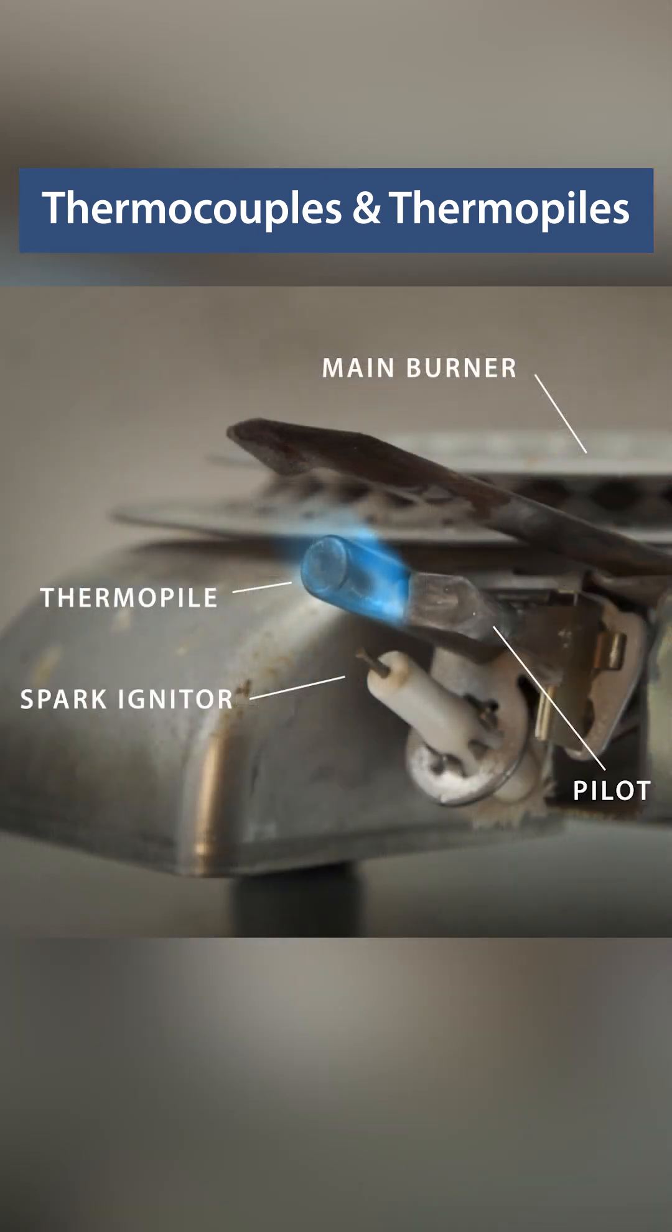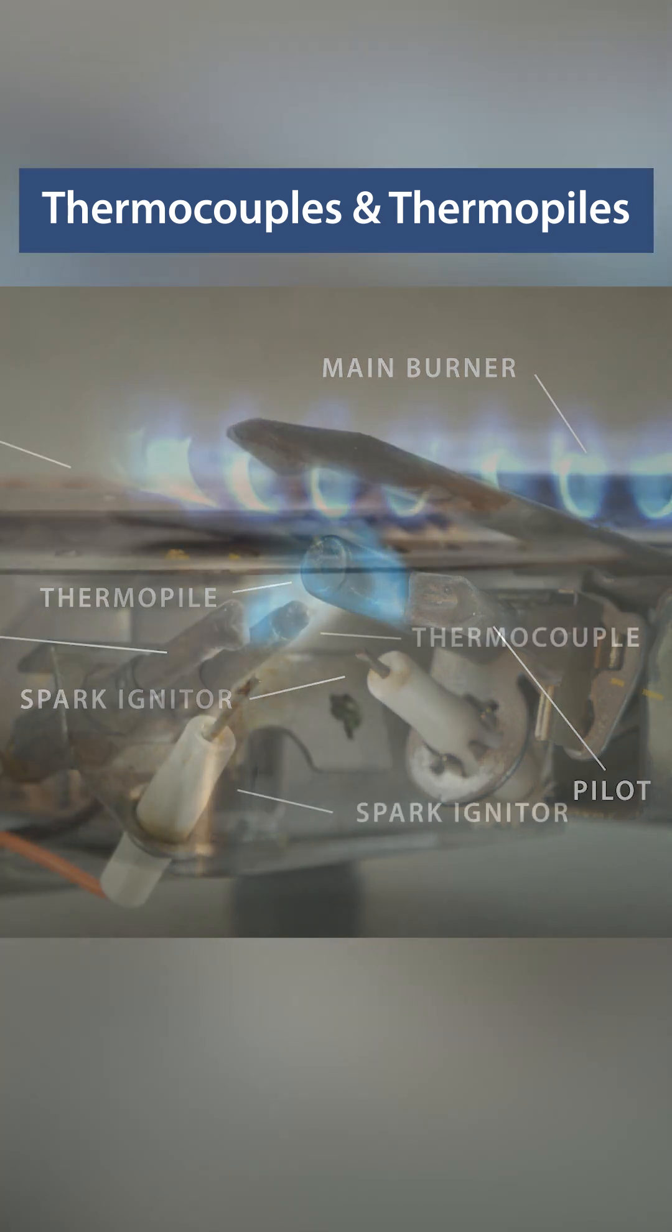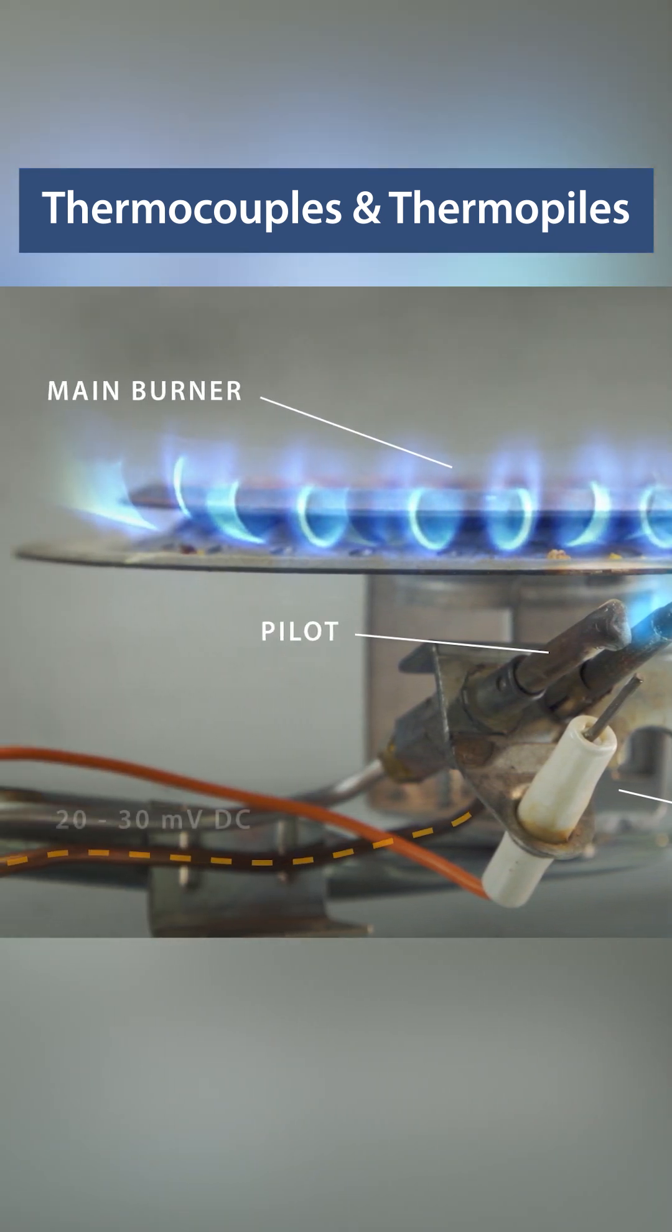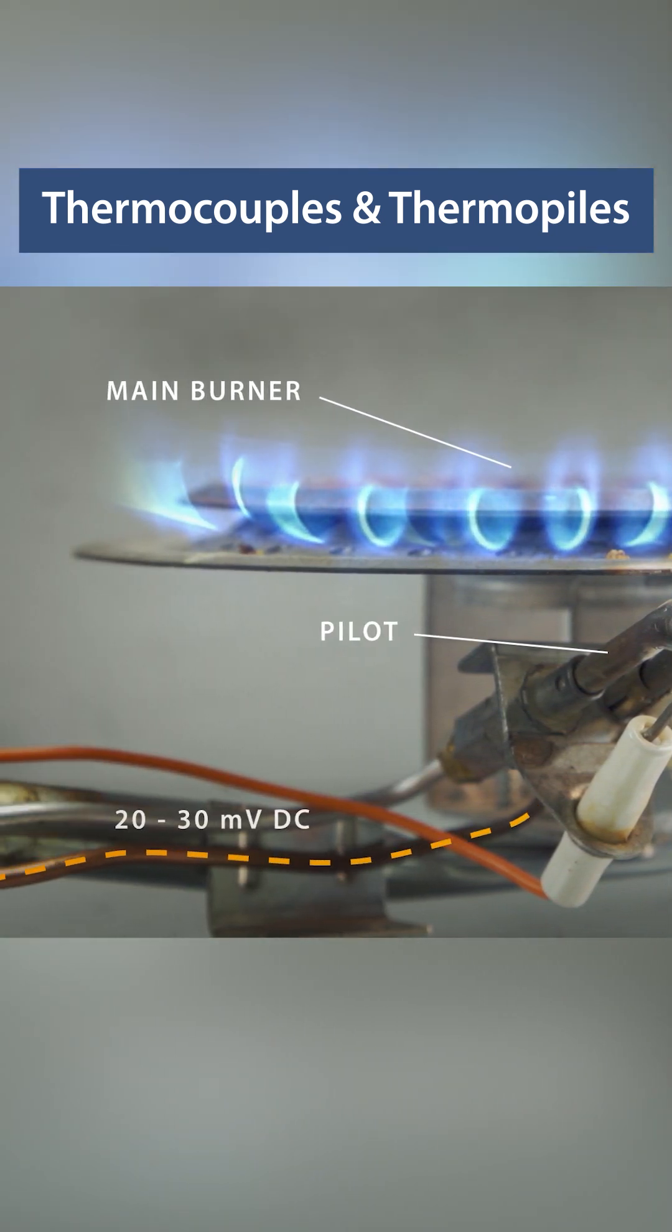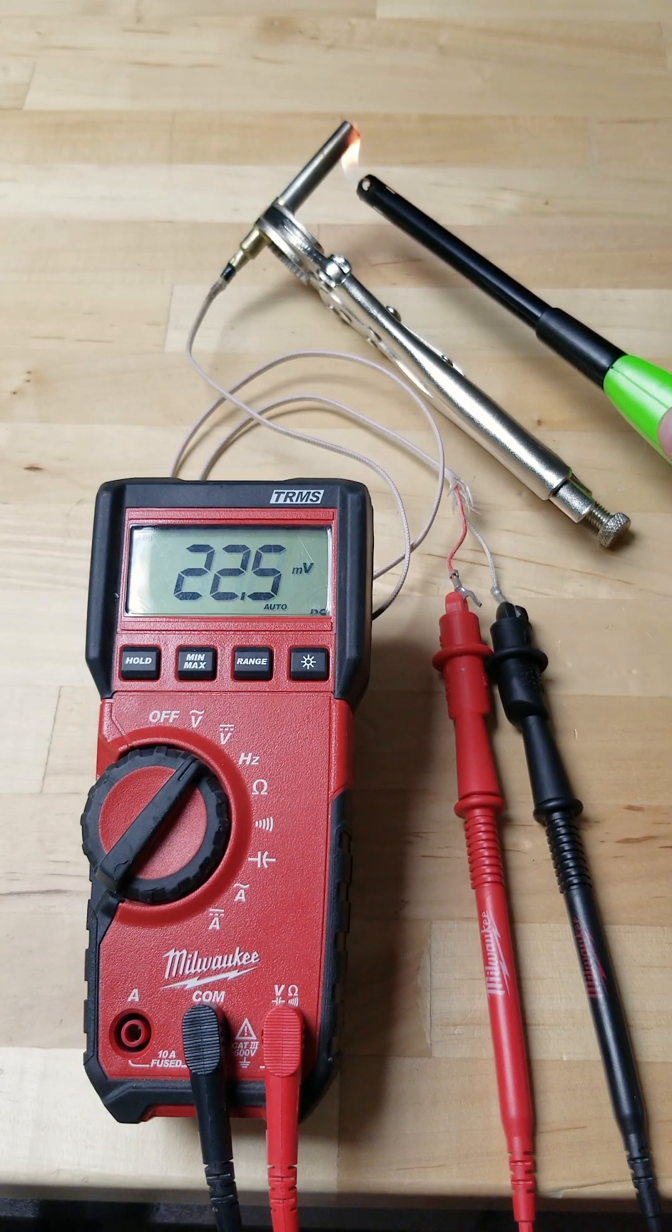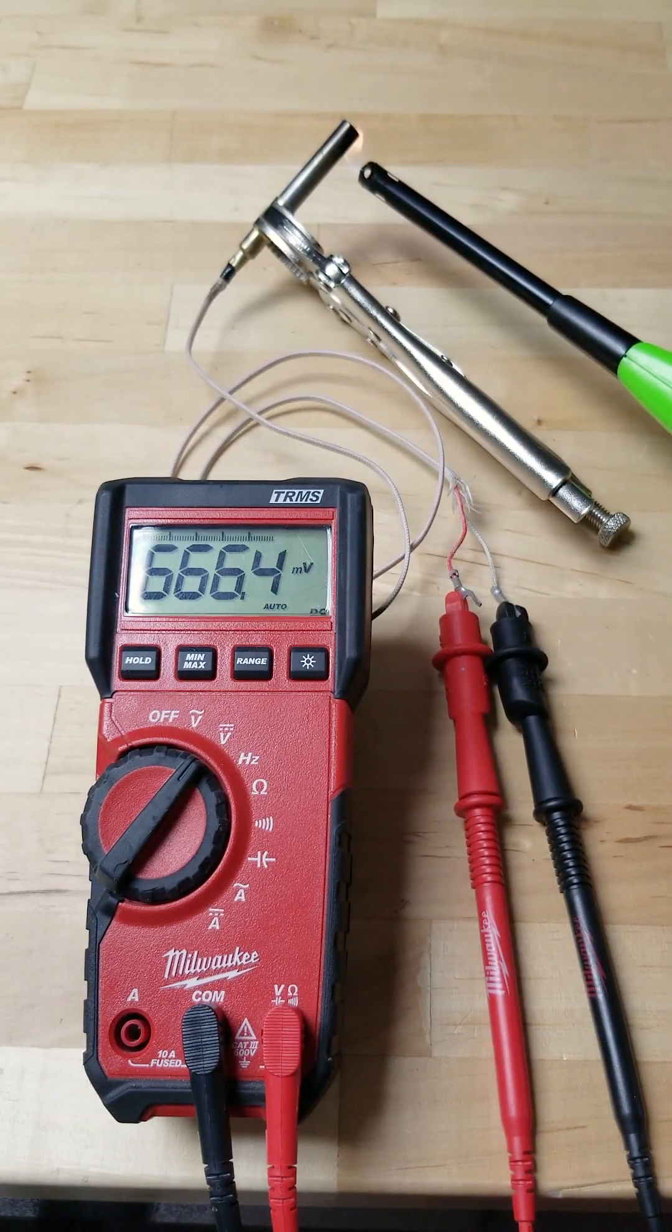Inside are two dissimilar metals that produce a small amount of voltage when heated by the pilot flame. Thermocouples are smaller and produce about 20 to 30 millivolts. A thermopile is several thermocouples bundled together and will produce up to 750 millivolts.